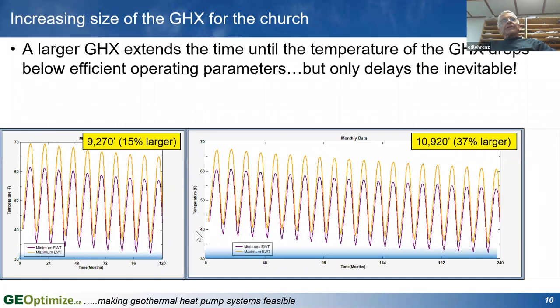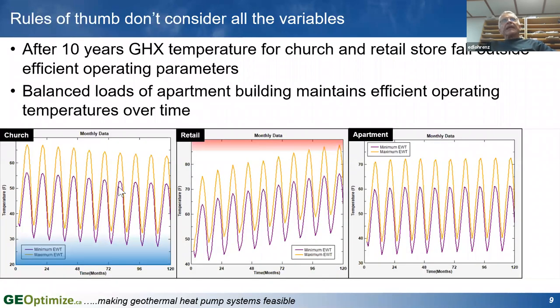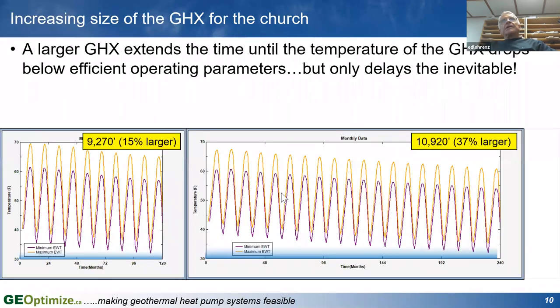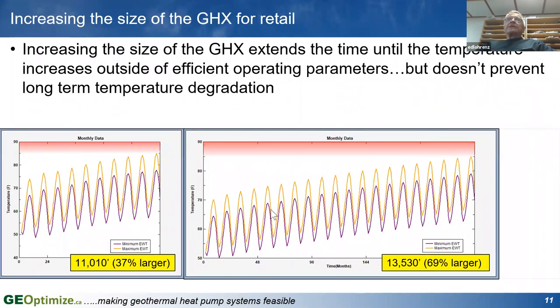So even if you're going to make the ground heat exchanger a lot larger, like here we're looking at about 8,000 feet of drilling on each. Here we've increased it to 9,200 feet of drilling, and even increasing it to 11,000 feet of drilling, all you're doing is delaying the inevitable decrease in temperature. Same thing in the store. This one, even making the ground heat exchanger about 69% larger, that's simply going to delay the inevitable.